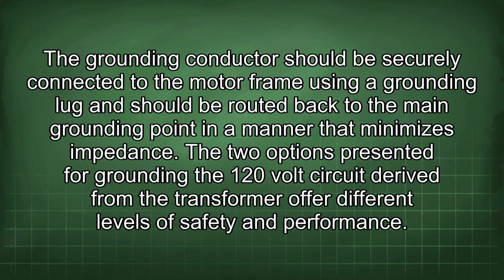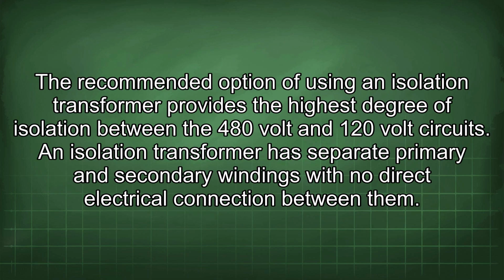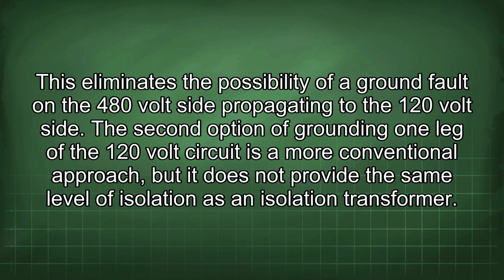The two options presented for grounding the 120-volt circuit derived from the transformer offer different levels of safety and performance. The recommended option of using an isolation transformer provides the highest degree of isolation between the 480-volt and 120-volt circuits. An isolation transformer has separate primary and secondary windings with no direct electrical connection between them. This eliminates the possibility of a ground fault on the 480-volt side propagating to the 120-volt side.